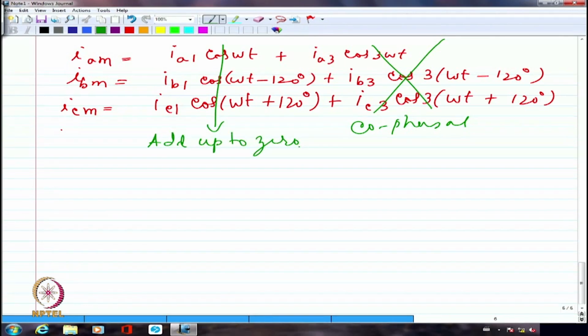Whereas because they are co-phasal, the sum is not equal to 0. So what is going to happen is, if I am having a star-star connected transformer, neither the primary is grounded nor the secondary is grounded. In which case, especially when I am initially energizing the transformer, I just turn on the power supply, I have not connected the load. At that point, the primarily drawn current is magnetizing current. Core loss component of current is definitely there, I am not questioning that, but that is mainly the magnetizing current.